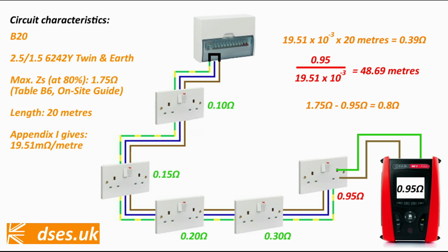But this being a 20 metre circuit means what we have here is a potential loose connection that's likely to worsen over time. And if you want to be assured that arc fault devices aren't going to cause you any trouble either immediately or further down the line, you're going to have to know for sure that your readings are right. And the way to do that is to also measure the neutral. Yes, often the only time the neutral is considered when an ohmmeter is waved around is R1 plus Rn testing on a ring circuit. And even then, that's usually on initial verification when commissioning a new circuit rather than ongoing inspection.